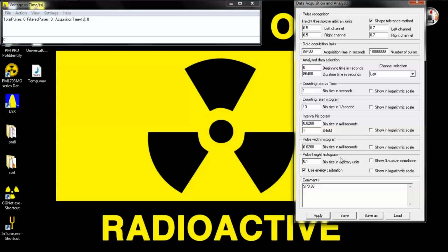Bin size in arbitrary units. This number here will affect how many little channels you have going across the bottom. It's almost a scaling number. If you set it too high or too low, you might find that you have too many or too few channels. I have it set to 0.1, and I'll show you in a minute what happens when I change it to a higher or lower number. That might make a little bit more sense to you.